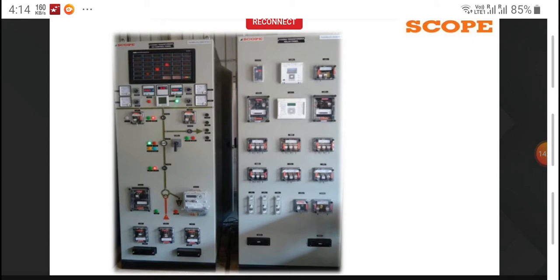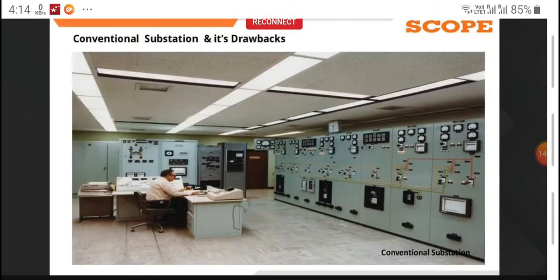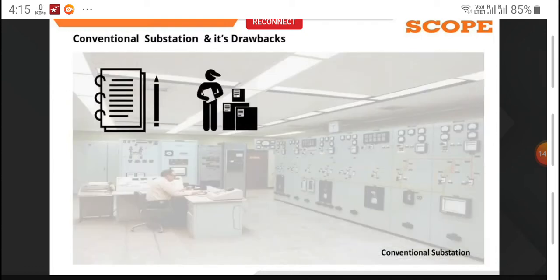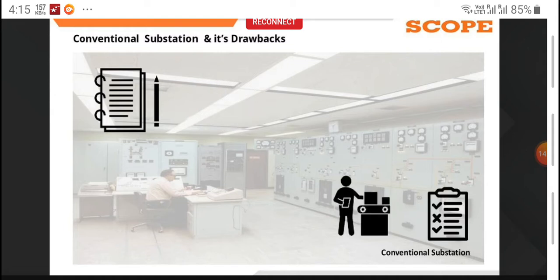You can see here the conventional substation, where the operator sits and monitors all the signals through the control panel. The main drawback of this system is manual intervention. Every time, the person who sits in that control room has to write everything down. He goes to the control panel, periodically takes the energy readings and puts them in the notebook, and comes back here and puts them in the ledger.